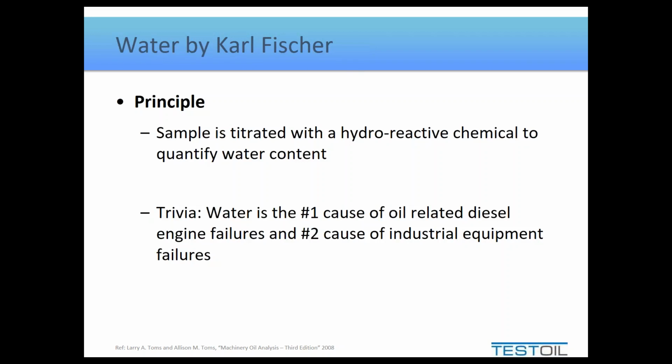But in this case, what we're trying to do is react out the water. So we use a hydroreactive chemical, and we measure how much of it we have to add to the system before it stops reacting, and that's how we know how much water we've reacted out of the sample.